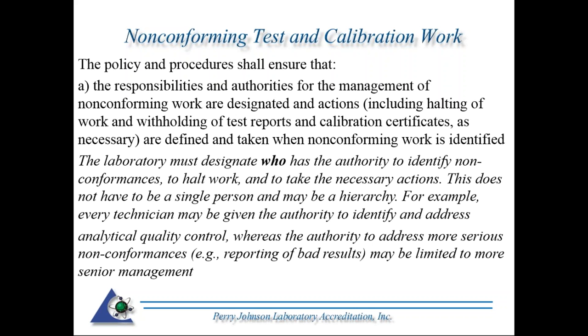Okay, I mentioned the policy and procedure has to ensure, and there's a list of items. Item A currently is the responsibilities and authorities for the management of non-conforming work are designated, and actions, which could include the halting of work and withholding of test or calibration certificates, are defined and taken when non-conforming work is identified. So in other words, the laboratory must designate who has the authority to identify non-conforming work, to halt work, and to take the necessary actions.